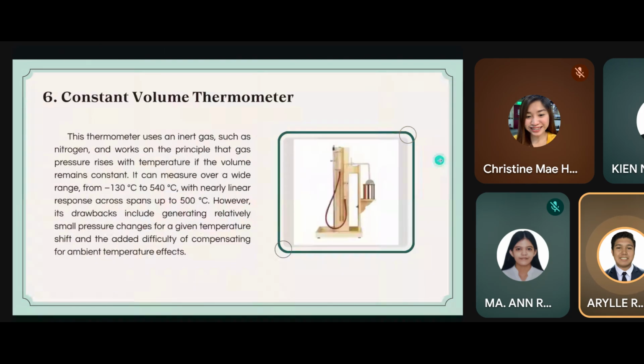Next is the constant volume temperature thermometer. This thermometer uses an inert gas such as nitrogen and works on the principle that gas pressure rises with temperature if the volume remains constant. It can measure over a wide range from negative 130 degrees Celsius to 540 degrees Celsius, with nearly linear responses across spans up to 500 degrees Celsius. However, its drawbacks include generating relatively small pressure changes for a given temperature shift and the added difficulty of compensating for ambient temperature effects.